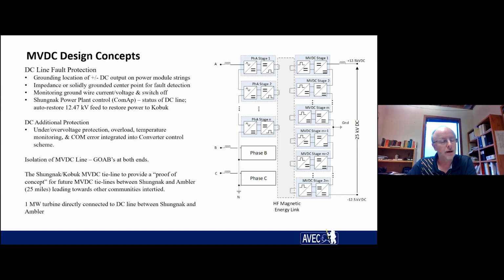One of the points on the DC line is we want to make sure that there's gang operated switches at both ends to completely isolate the DC line. Also, any devices that could potentially be opened by a lineman, we want to make sure that they have key interlocks with the converters, so that we don't open up the GOABs, which are not rated for DC. So the line would have to be completely dead before those could be opened.